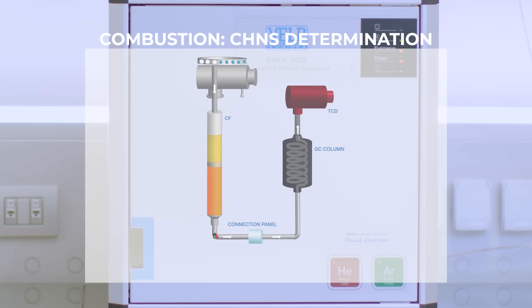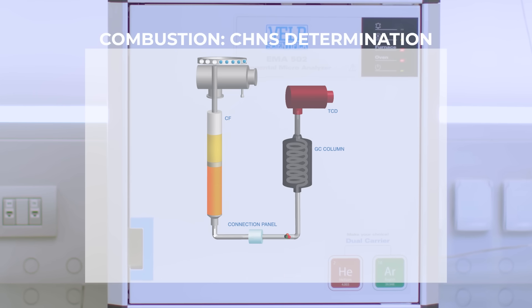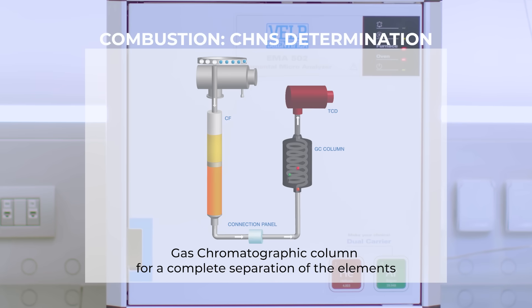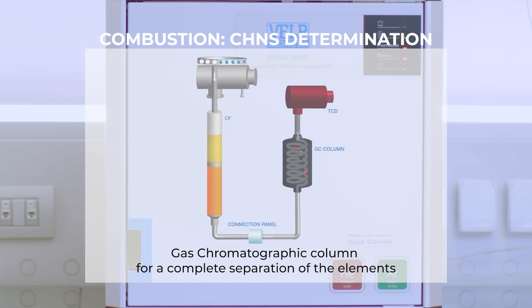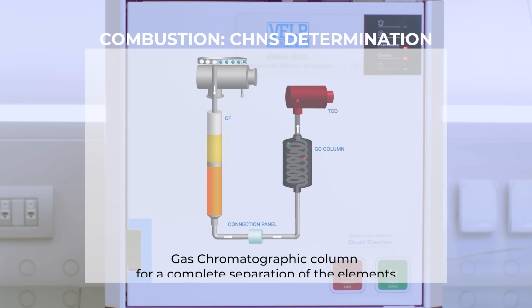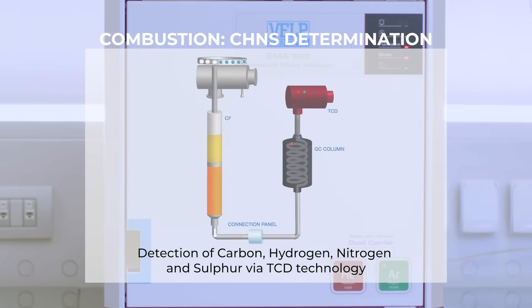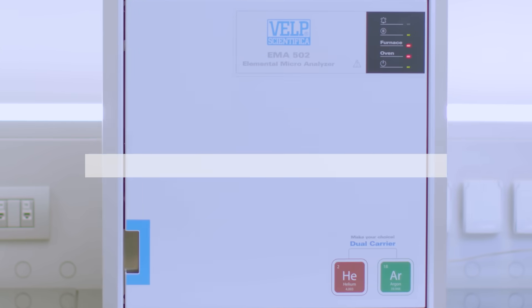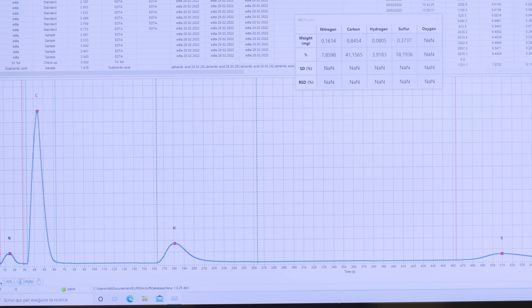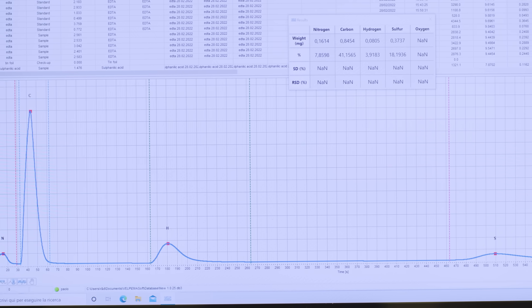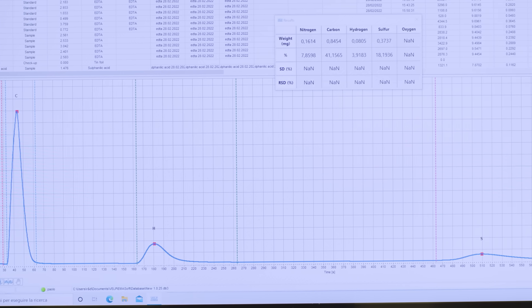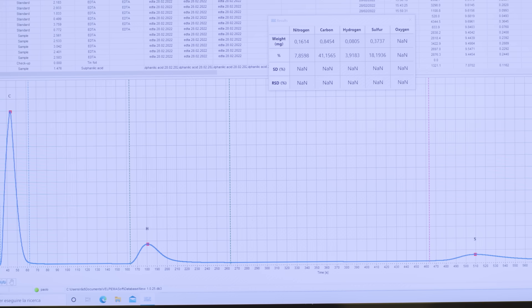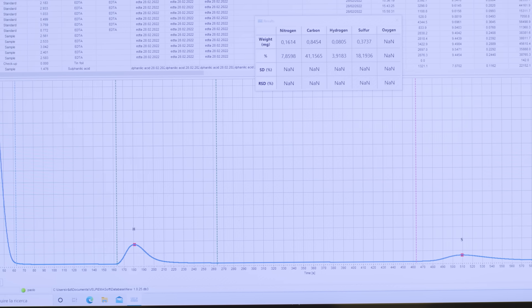The flow passes through the connection panel and then reaches the gas chromatographic column oven, which ensures homogeneous and modular temperature, leading to a complete separation of all the elements for the final detection by TCD. The EMAsoft real-time graph shows all element peaks for a detailed understanding of the analysis progress.